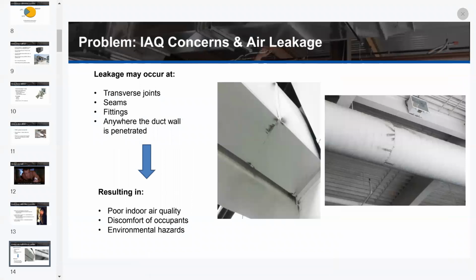So typically leakage with HVAC systems is due to air leaks at the joints, seams, and fittings. As you can see in these two pictures, on the left we see duct leakage at slip and drive seams, shown by evidence of that black residue. We also see energy loss at the seams of the spiral duct on the right. And that could be either a positive pressure leak or negative pressure leak, creating turbulence around that area, pulling any dirt and debris out of the air and depositing it on the surface, or, if the duct system internally is dirty as well, it could be pushing some of that debris out of the duct system.